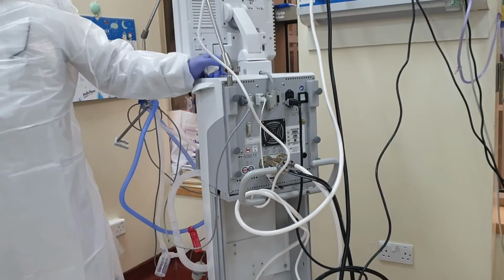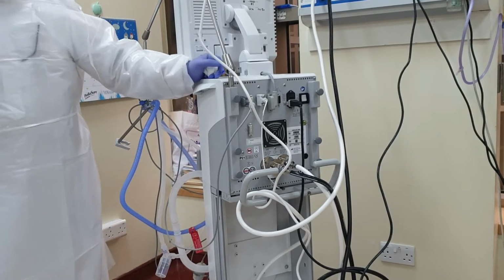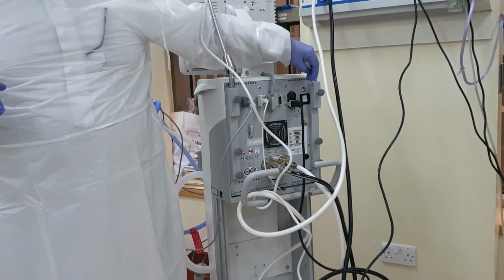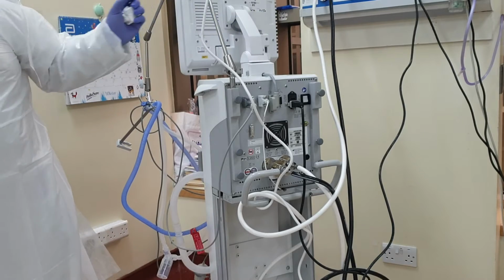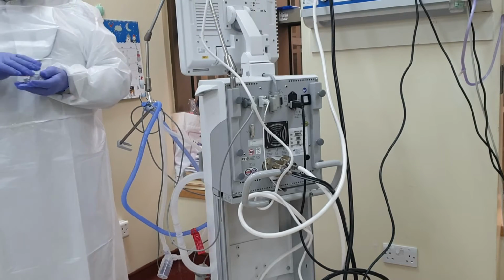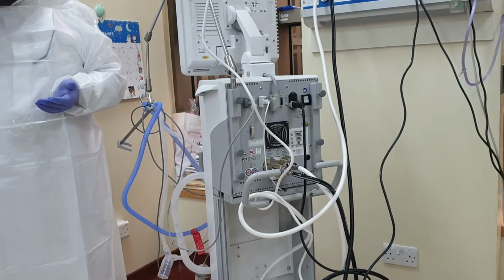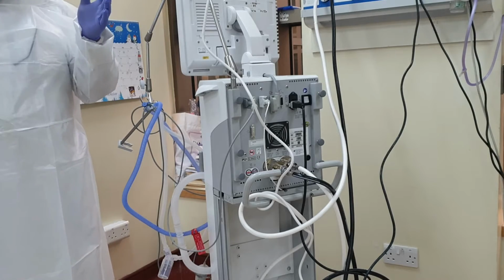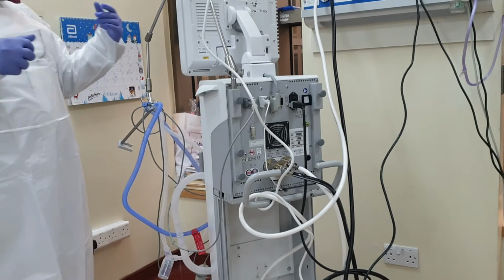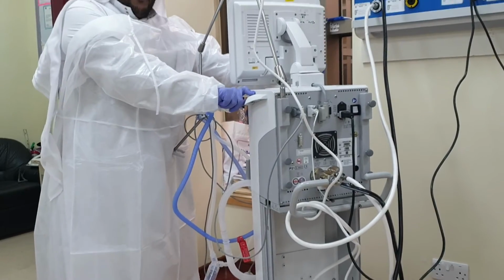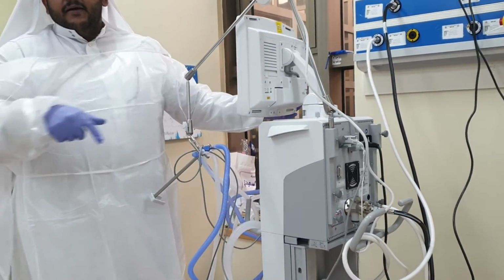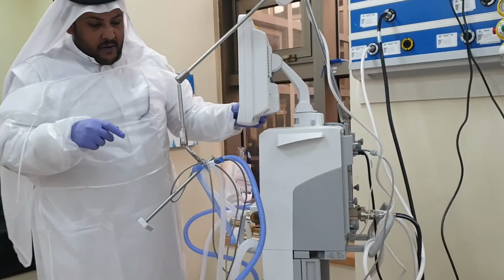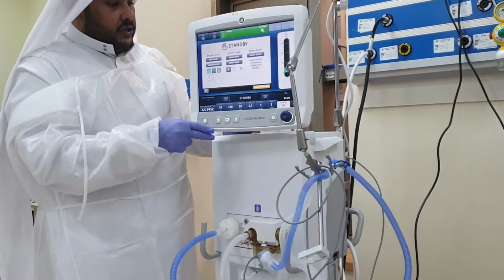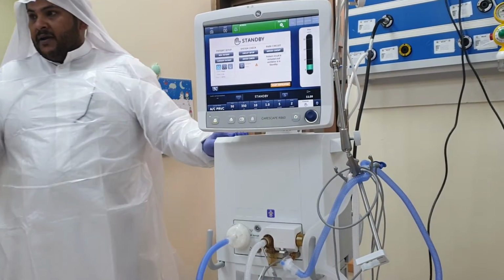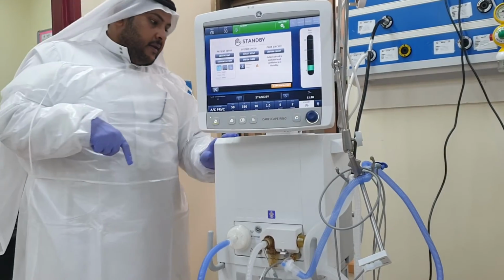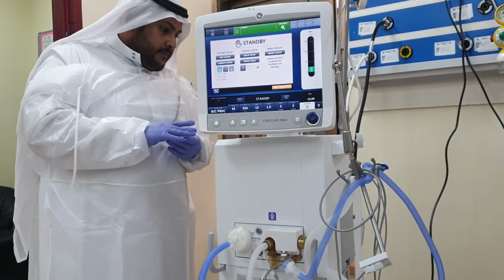If the ventilator was on, working with the patient, and someone accidentally hit that one, what would happen? The ventilator will continue working. The ventilator will not shut off except if it was in standby. So now we are in standby. If I turn it off, it's going to go off. But if it was working on the patient, it won't have this issue. It will tell you to go to standby first, then shut off the ventilator.